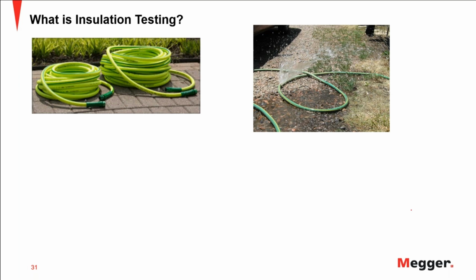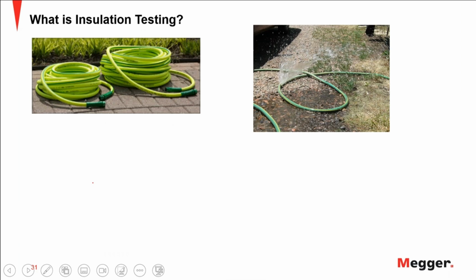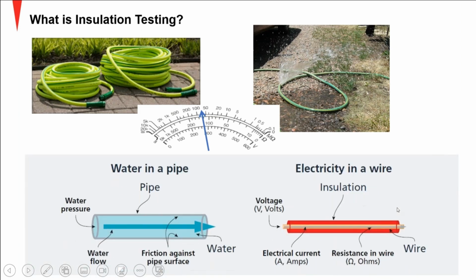What is insulation testing? Basically, it is the measurement or the test that you perform to determine if you have a good quality insulation, basically a test to determine if your insulation is containing all your electrons there. I use this sentence as a segue to the analogy that we have here. Electricity in a wire is like water in a pipe. If you have water with low pressure in the pipe, you might have a pipe or a hose with a defect, but because there's no high pressure there, you're not going to have a leak. But if you increase the pressure, well, this is what could happen. And you have a leak, and the more pressure you apply, the more leakage you have.